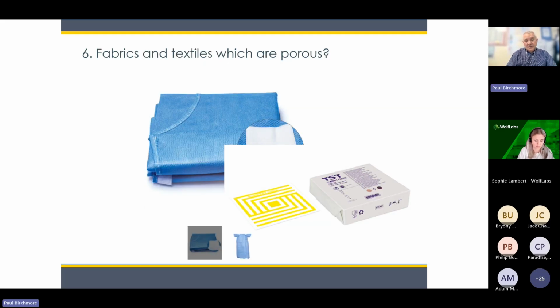But in this case, you might think, well, okay, you've got your dry system, but how do you prove you've had full steam penetration during this process? And you might have to include a test mechanism, which for textile materials is often a Bowie-Dick test, whereby you put a heat-sensitive, steam-sensitive item, a test card, inside the load and check for the result before and after. Then you can prove that you've had full coloration of that test card, which will give the evidence of the full steam penetration within the load.